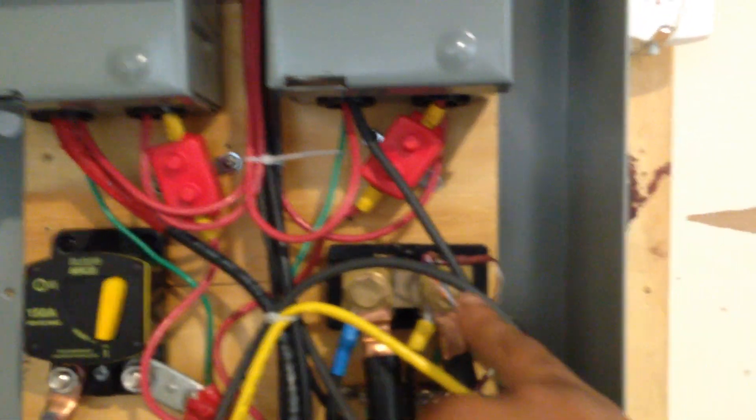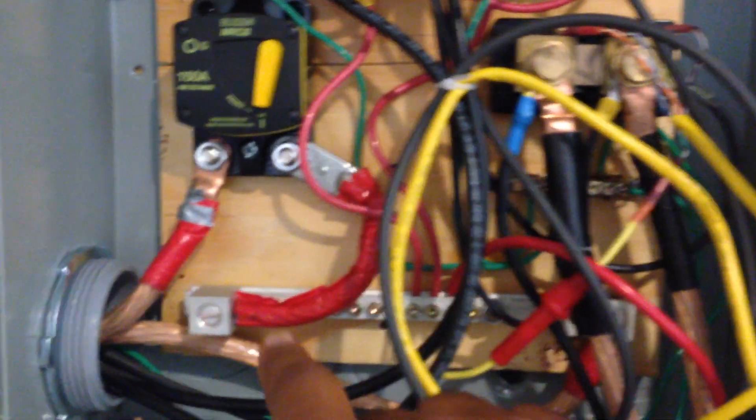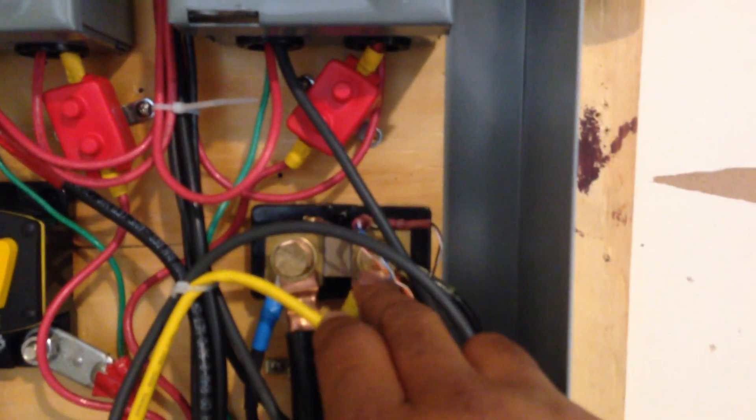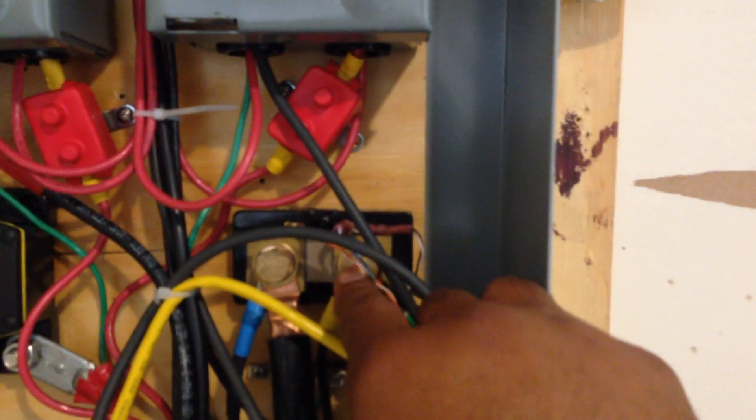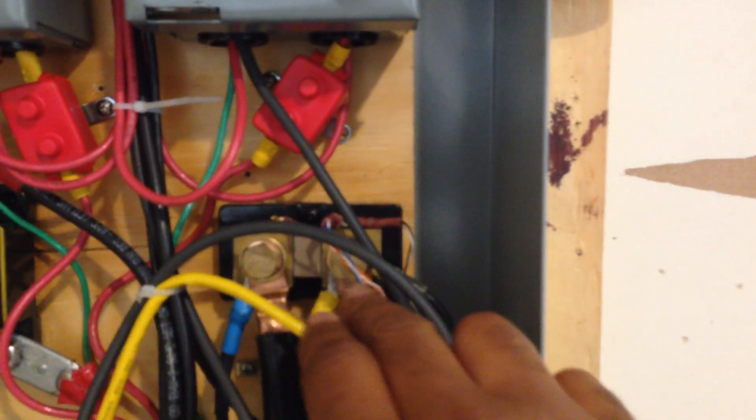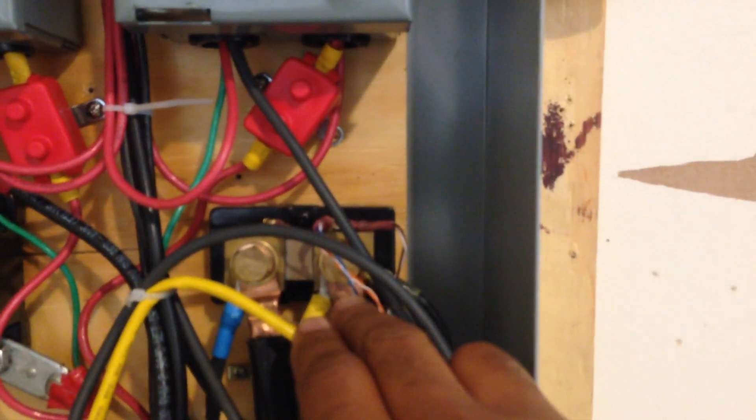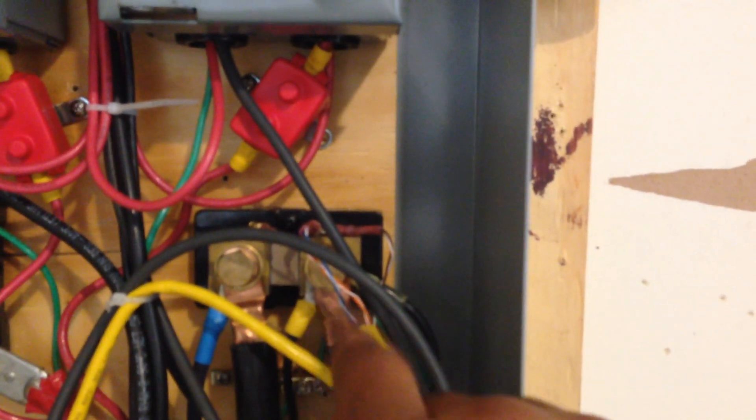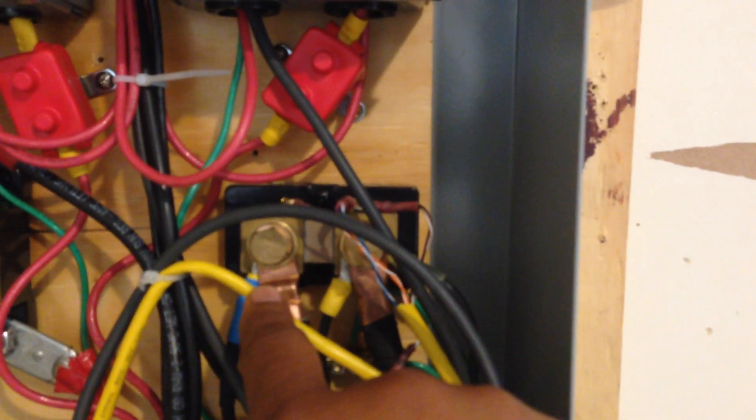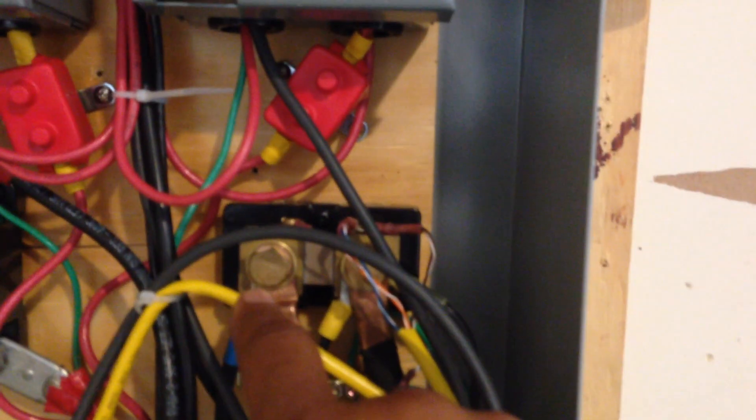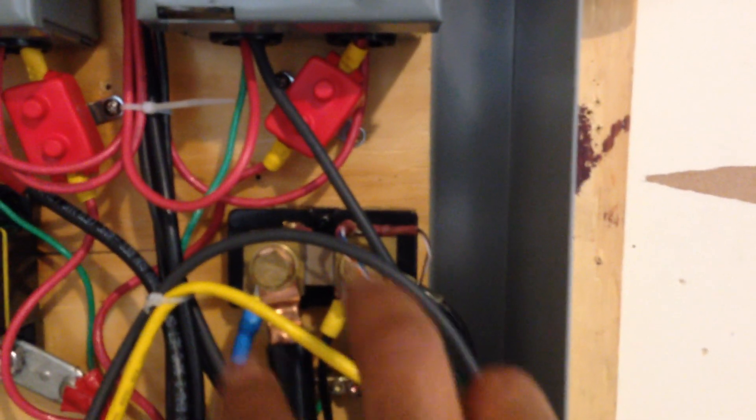With these MPPTs, they do the job. They do the job well. They're coming in and the negative is tied together on this shunt. And the positive is on this positive bus bar. So on this side of the shunt, at this particular bolt or screw or right here, this lug, this is where my trimetric is. And this tells me what's coming into the battery and what's going out. On this lug, this is where the actual negative cable to my battery bank is connected.